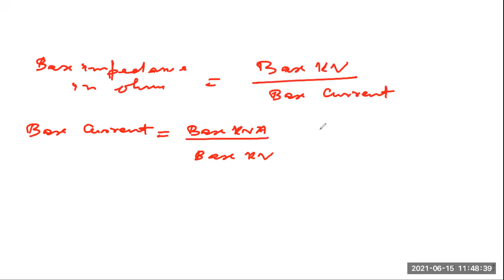So this is the base current calculation by base kV. What will happen, you see here, this kVA will cancel, so it will be in unit. But here it is base kV, so kV we need to convert to volt. So what we'll do: this will be base kV into 1000, the whole square, divided by base kVA. Now is it clear? Is it clear?